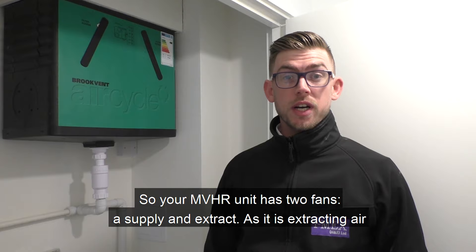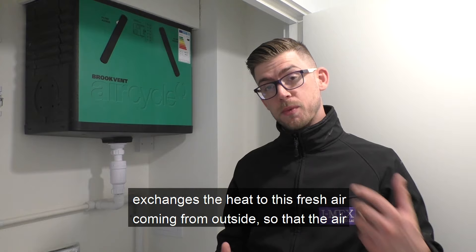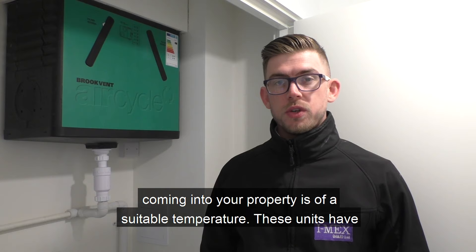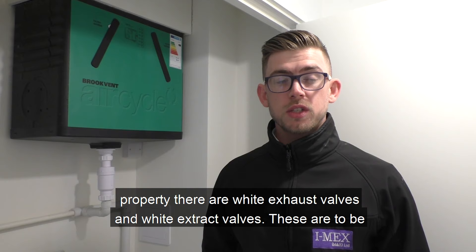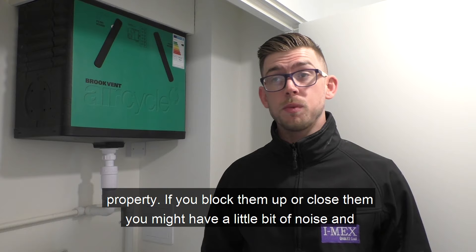Your MVHR unit has two fans: supply and extract. As it's extracting air from your property it goes through a heat battery within the unit and exchanges the heat to the fresh air coming from outside, so that the air coming into your property is of a suitable temperature. These units have been professionally commissioned by our engineers on site. Throughout your property you'll notice white exhaust valves and white extract valves, which are to be left alone. They are commissioned to have a certain gap so they have a certain flow rate going through them depending on the size of your property.